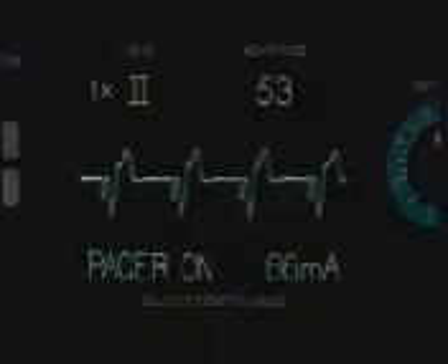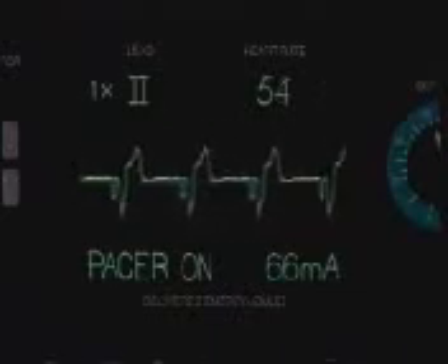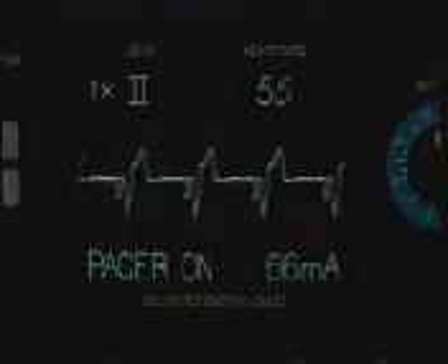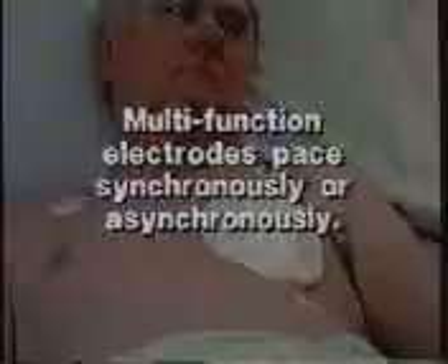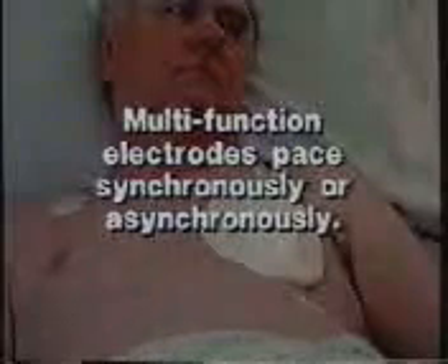3 standard sensing electrodes in right arm, left arm, and the left leg position connected to the ECG cable will additionally provide monitoring leads 1, 2, and 3. In the pacing mode, only leads 1, 2, and 3 are accessible. Standard electrodes need to be applied to observe and sense pacing on the monitor screen. Multifunction electrodes will pace either synchronously or asynchronously depending on the application of the 3 sensing electrodes.